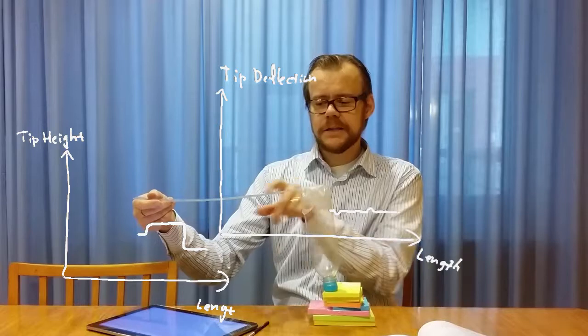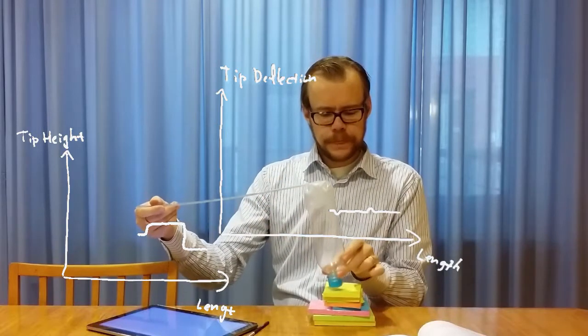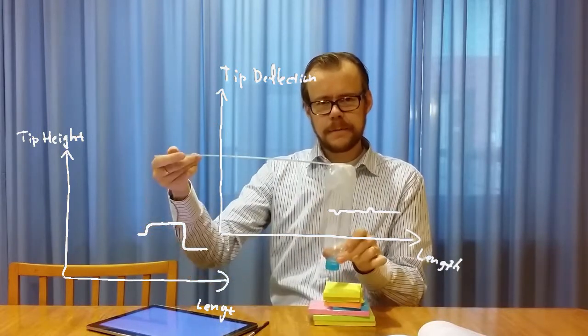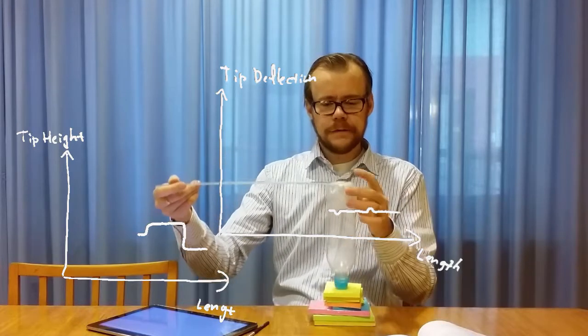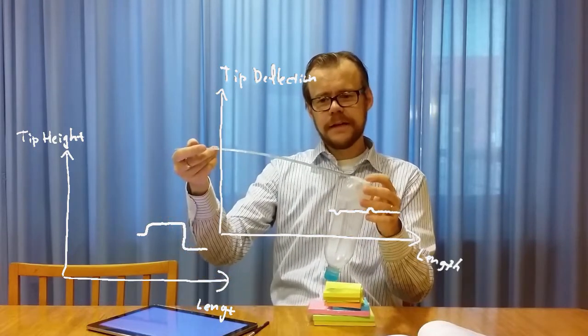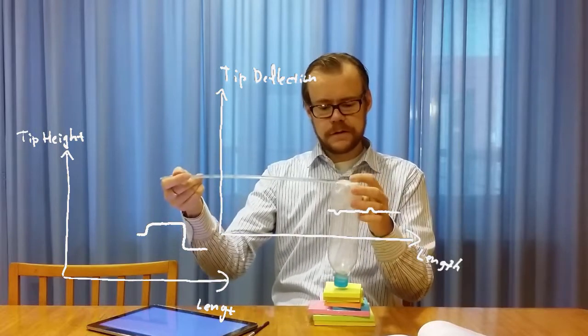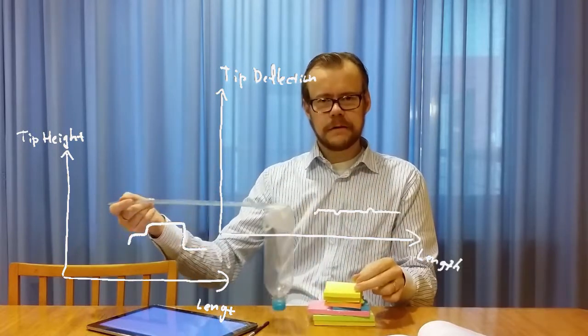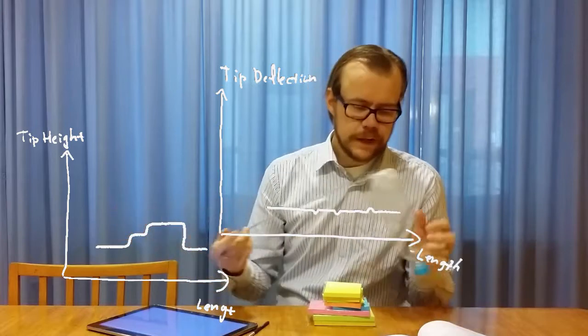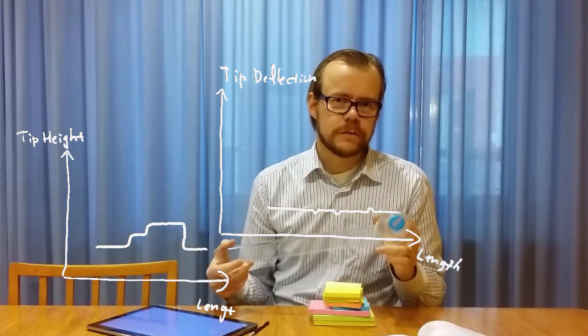Because as soon as I get into some obstacles the tip will deflect up and I will notice, measure this change in deflection of the tip. And then I can compensate by raising the tip up from the sample, and if the tip is raising too much it will deflect in the opposite way. So then I can keep this at a constant position while it scans.